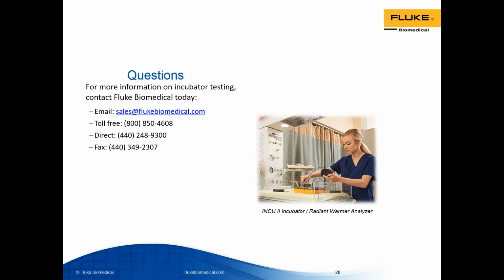All right, next one. Why is simultaneously testing all parameters at once recommended? What's the difference if I just use handheld instruments to make my measurements, not an analyzer? That's a really good question, and we touched on this towards the end. So, getting a full picture of what's going on inside the incubator is extremely important. So, what's going on with temperature at the same time as sound being mapped with airflow, because all of these parameters work in conjunction with one another to make the incubator a stable, uniform environment. And the problem with using, just like a handheld test tool for temperature and then another one for airflow is that you're not getting the full picture of what's happening. And also, most of the time, that requires opening a porthole and putting your hand in there and putting the sensor in, at least one of the sensors, and that disrupts the whole test environment as a whole.